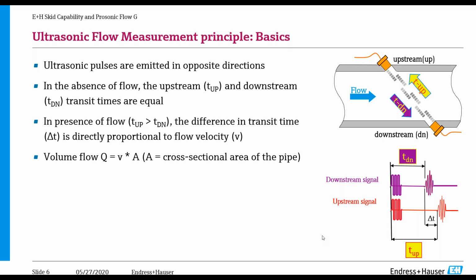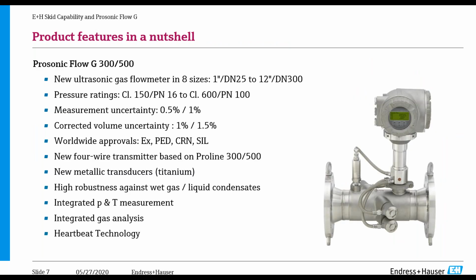You can have multiple transducers in the pipe, but for demonstration purposes, we only show one here. And that's the basic measuring principle. Sound travels faster with the flow and slower against the flow, and we measure that time difference. And the reason this is important, so that is the basics on the flow.